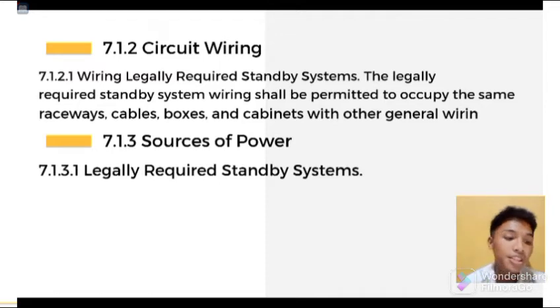So the battery shall be of a suitable rating and capacity to supply and maintain not less than 87.5% of the nominal battery voltage for a total lamp load associated with a unit for a period of at least 1.5 hours. So the unit equipment shall be permanently fixed in place and the flexible cord shall not exceed 900 mm in length.